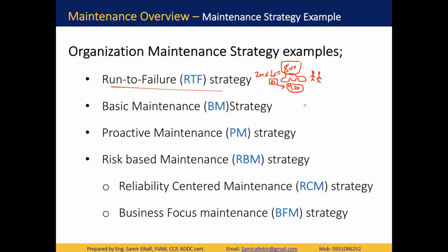a new one. But in almost the same case, imagine a similar type of pump capacity. It's a jockey pump in the firefighting system. You have the diesel pump, the electrical pump, and the jockey pump. It's very small. Can I say I'm not going to do a PPM for the jockey pump, and I will let it run to fail because the maintenance will cost me more? Even if this was the case, 800 to 900, still I'm not going to do that.